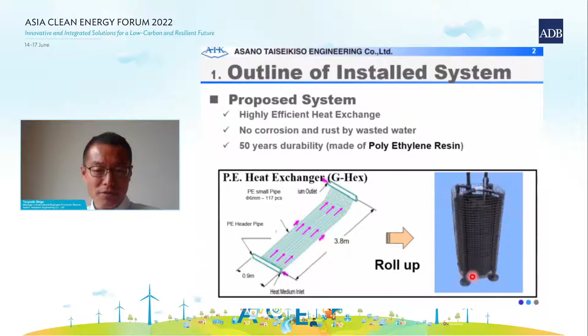The chicken processing factory uses very cold water, 0 degrees Celsius, for their production. The cold water is made from industrial water at 30 degrees Celsius by an electric chiller. The wasted water is still very cold, 2 to 3 degrees Celsius, and this coldness is now discarded. This heat exchange system utilizes the coldness for cooling the industrial water by 5 to 7 degrees. This is called a pre-cool system, and it's useful to reduce energy cost and CO2 emission from the factory.